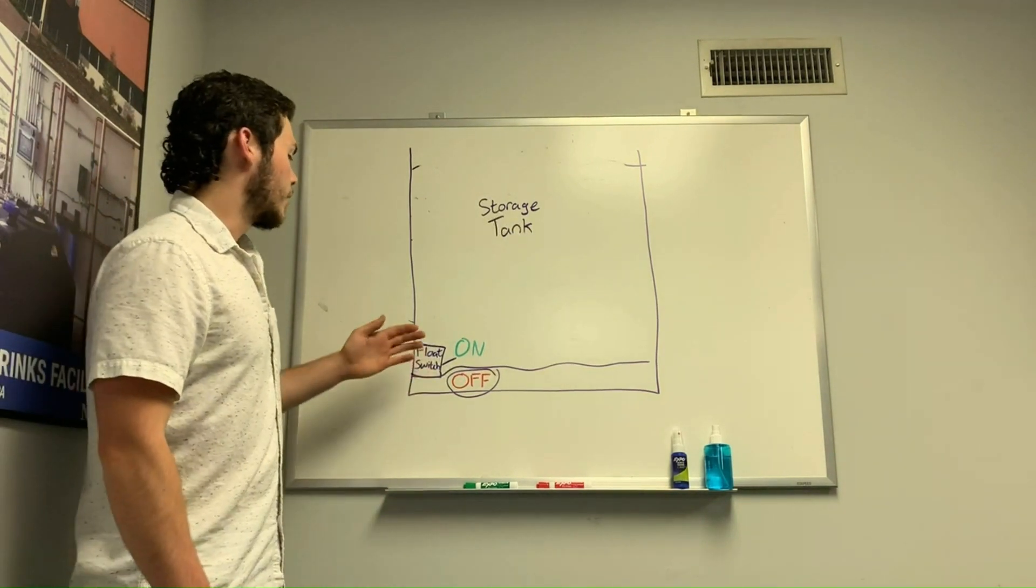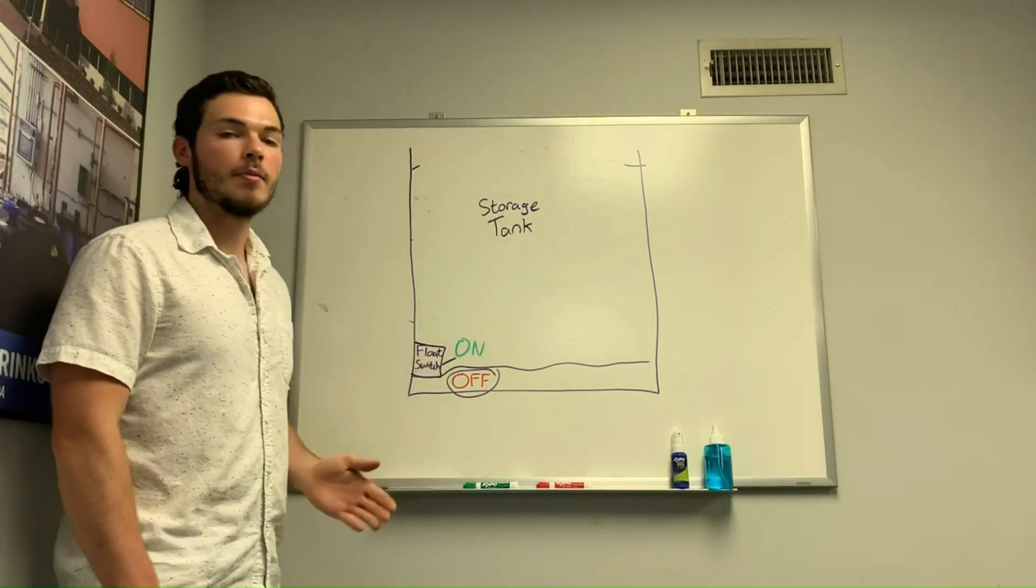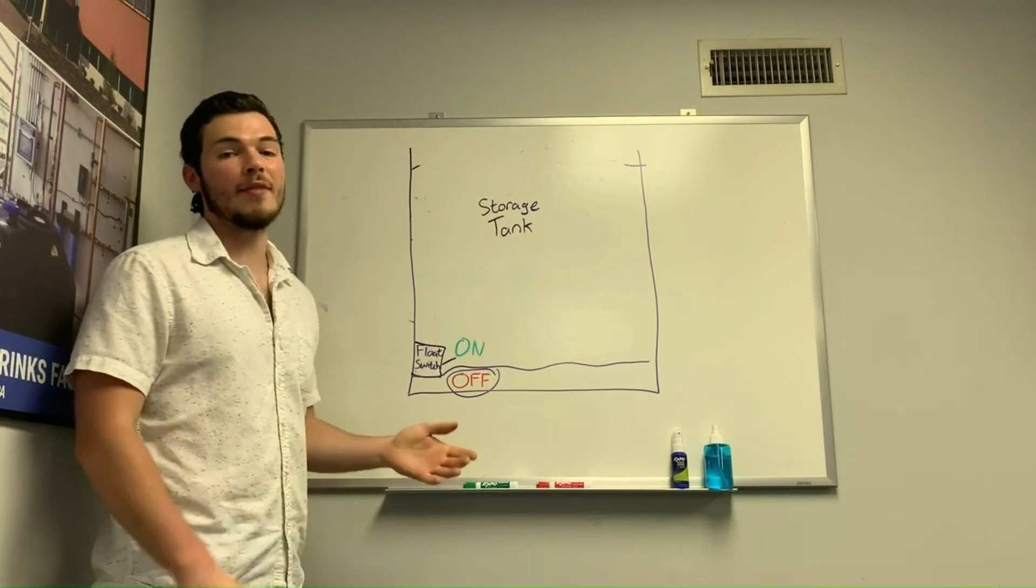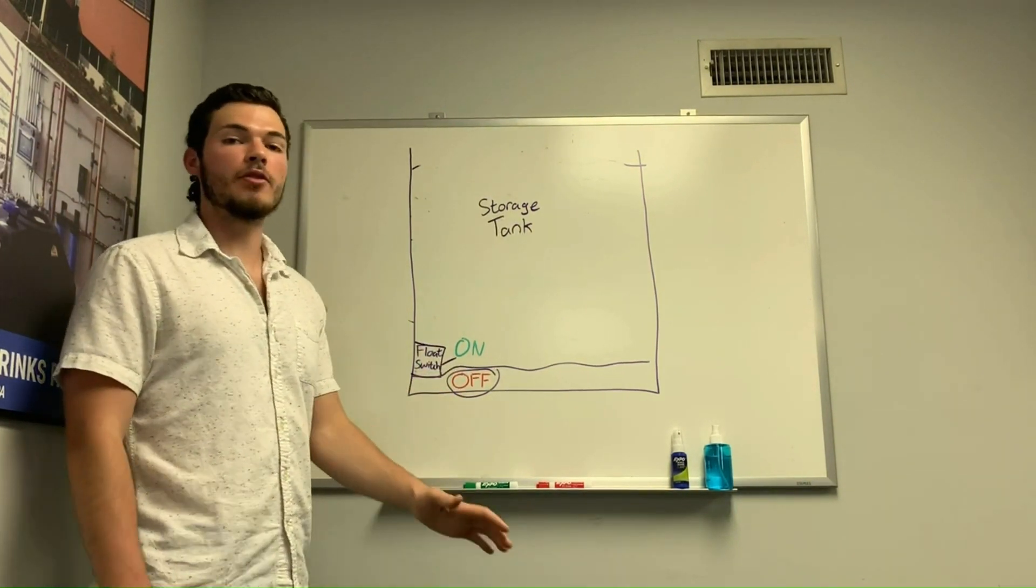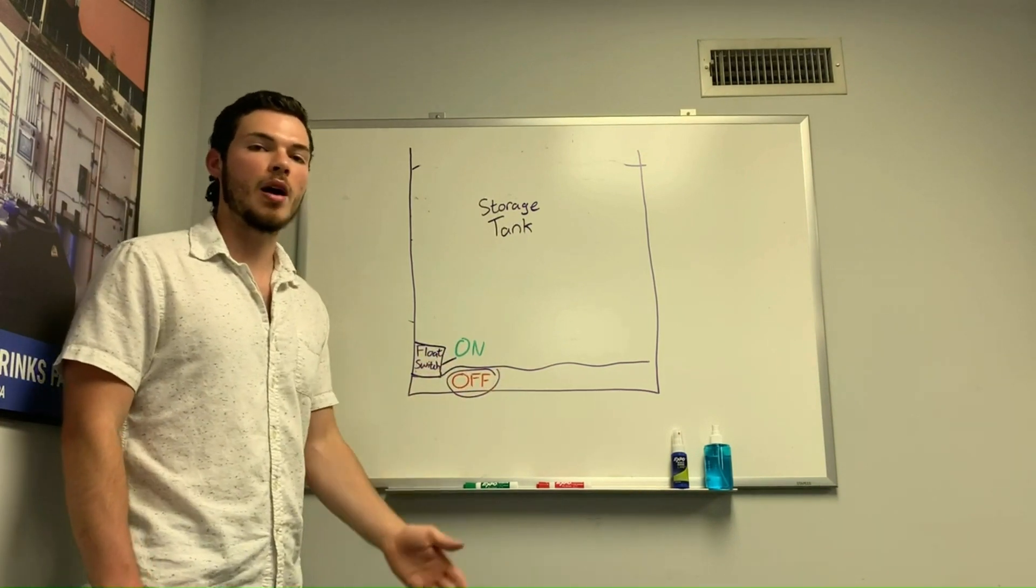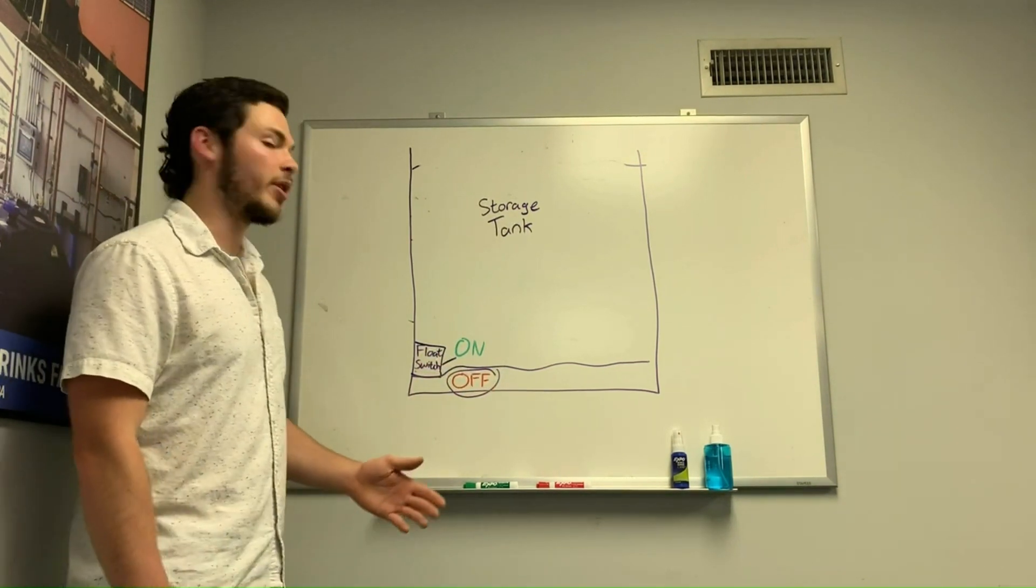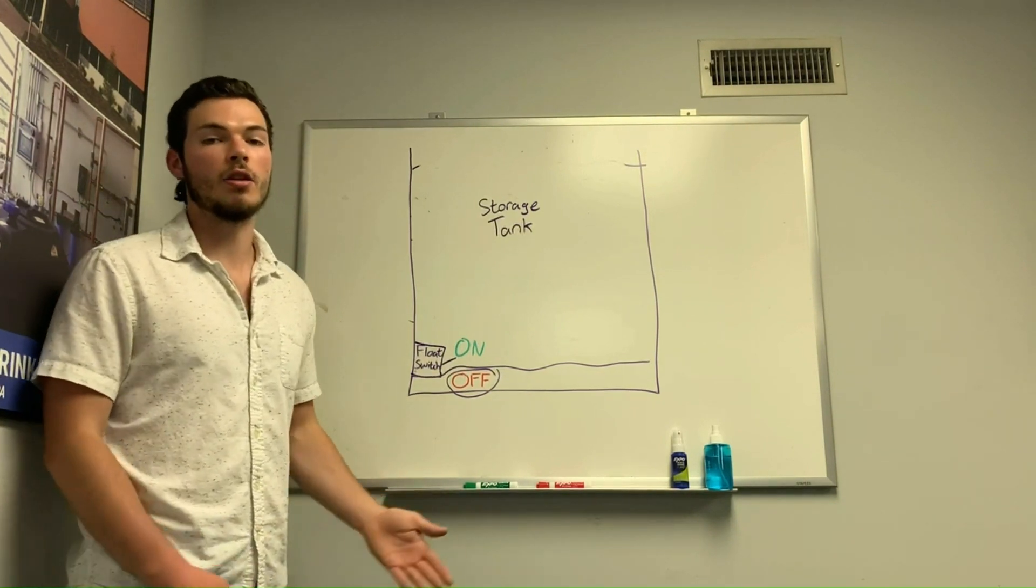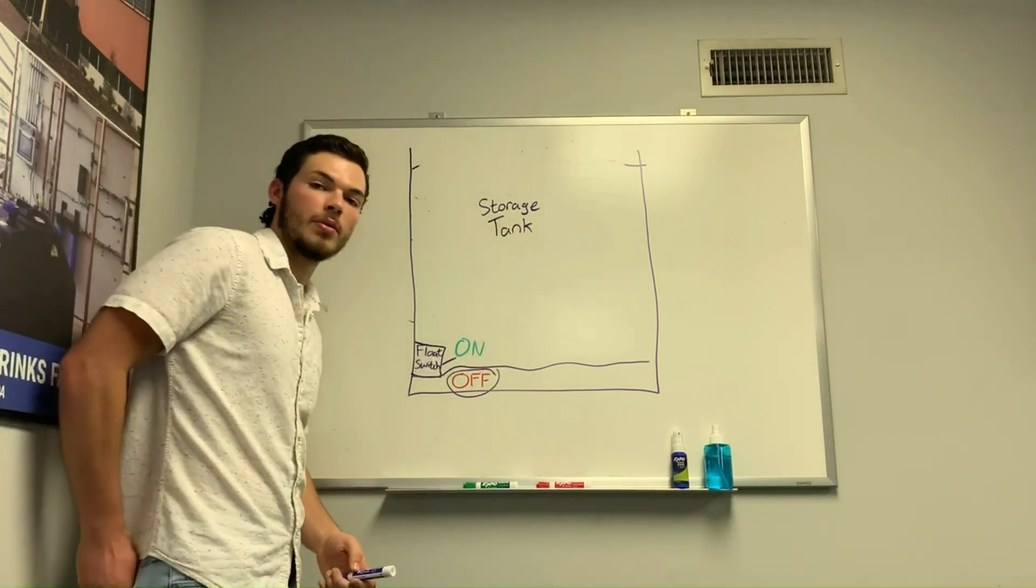They're often at the bottom of the tank because we don't want the tanks to empty all the way. Usually we have sediment settling to the bottom of your tank and we don't want to pump all of that sediment through the pump - it will damage the pump. Also, we don't want to empty the tank all the way so that the pump starts pumping air. That's called dry running and it will also damage your pump.